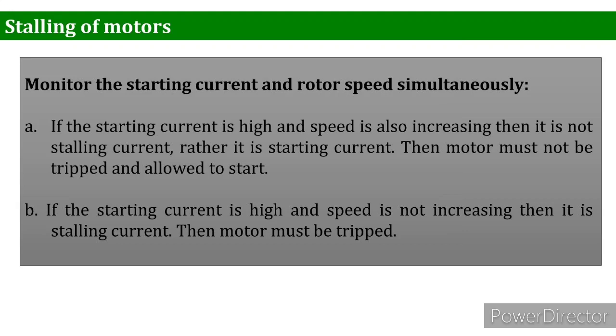If it is not tripped, then the rotor draws an excessive amount of current until the winding gets damaged, because there is no overcurrent protection installed at that time, so this factor needs to be focused on. This is the first condition, because you have to discriminate between the starting current and the stalling current. An induction motor draws about 8 times as much current while starting, so if a person does not know that, they might think the current is increasing abnormally. So you need to understand what is stalling, and what is proper operation, or the starting current.